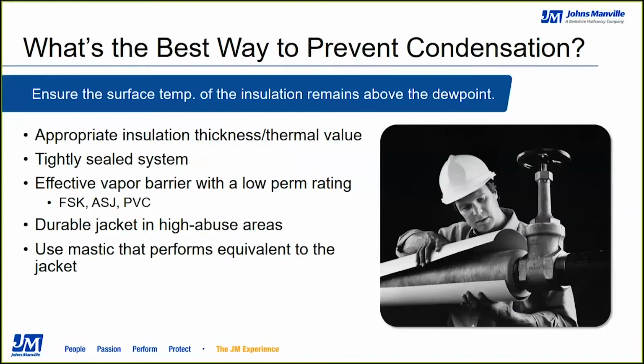Moisture operates a little bit like heat, where heat travels from a high temperature to a low temperature. Moisture is driven from high moisture content into lower moisture content. And because of that, you do need to create a barrier to prevent that moisture drive from occurring. Typically, that can be done with vapor barriers like FSK jacketing on duct wrap, for instance, or spin glass boards. Could be an ASJ facing, or an all-service jacket, like can be found on our Micro-Lok pipe insulation or on the spin glass board.